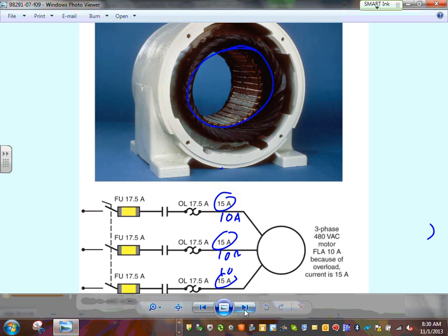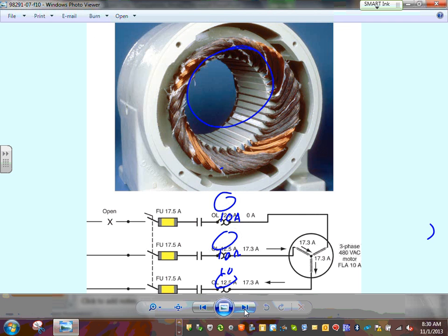This motor has overloaded and burned. Does that make sense? Overloaded and burned. How do you overload the motor? The mechanical machine on it, you're adding more load on it. Okay, so I want you guys to look at the chart inside of this motor. That's overload. Now look at this condition here. Compare this one to this.